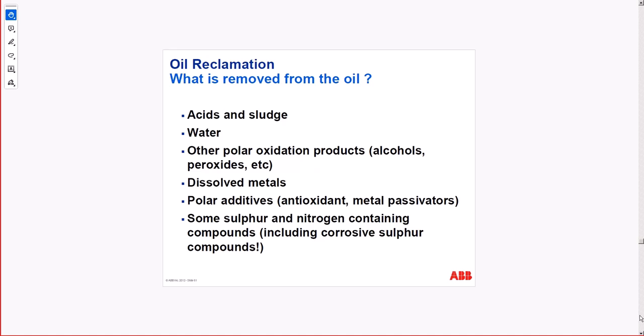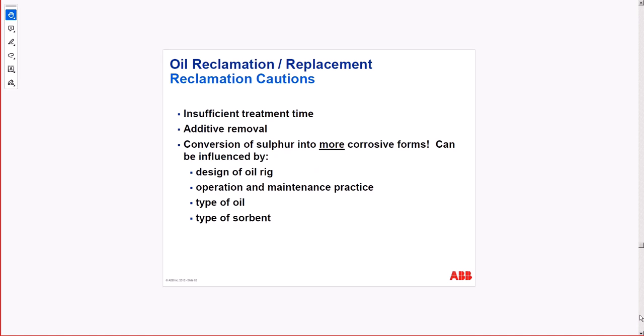The oil should be as clear as possible after this, close to a light yellow, not dark black. You can add antioxidants and other nitrogen compounds to slow down corrosion. Okay, so insufficient treatment time. When the reclamation doesn't go right, because it wasn't done properly in the time that you need to allow, 24 to 48 hours, it may happen that the sulfur converts into more corrosive forms because of the incomplete reclamation.